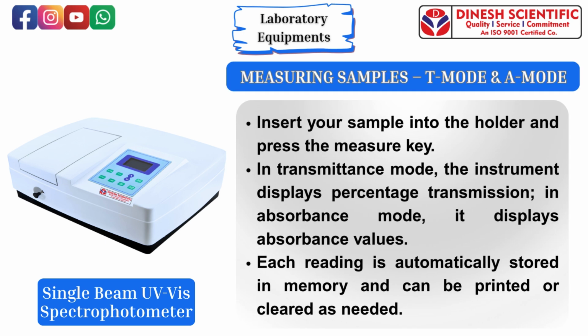Measuring samples, T mode or A mode. Insert your sample into the holder and press the measure key. In transmittance mode, the instrument displays percentage transmission. In absorbance mode, it displays absorbance values. Each reading is automatically stored in memory and can be printed or cleared as needed.